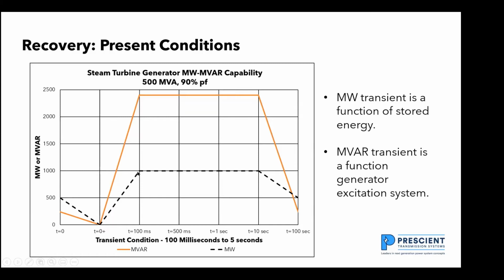100 milliseconds, the fault is cleared, and the kinetic energy can come out of the machine, and the machine can put out more than its rating for some short period of time. And here I'm showing it's 10 seconds. The machine can also put out a lot more MVAR for a short period of time. The only thing that's going to limit the MVAR capability is the machines come with VAR limiters, and the VAR limiter is going to kick in somewhere around 10 seconds. So this is showing the machine can produce, for a short period of time, much more energy than it can produce under steady state conditions.